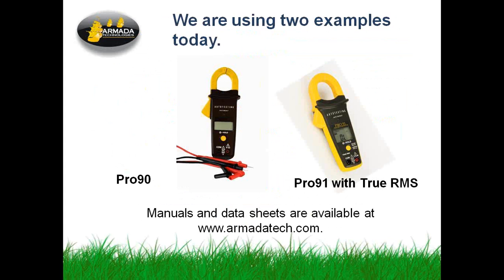The things we're using today are examples from the Armada product line. We have a line of meters, and these two automatic clamp meters are in the middle of the line and offer some real benefits. The Pro90 is an automatic clamp meter, single button control, and an averaging type meter, and the one on the right, the Pro91, is a true RMS meter, clamp meter, very similar to the 90, except that it has that computing power of true RMS built into it, and it's necessary for certain kinds of systems like LED lighting, as you'll see.